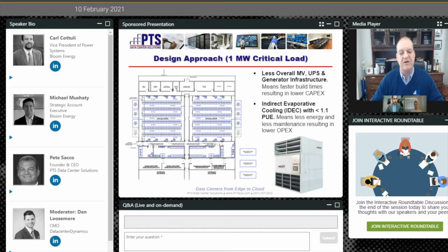And you'll notice I'm putting them compartmentalized on opposite sides of the building, because what if you wanted to scale this design? The easiest way to do this is to either A, stack up, or B, book match, meaning—and you could see the grayed out perforated lines—just flip the design on its short edge. Duplicate the power rooms for power room number three, power room number four, duplicate to data suite number three, data suite number four, and then here's where the beauty of it comes.